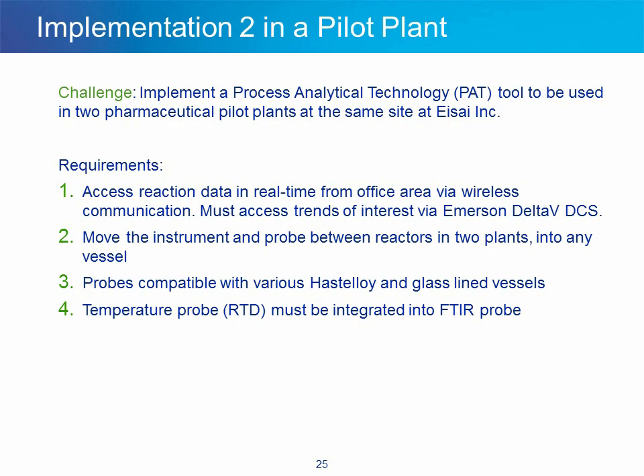Implementation number two is in a pilot plant. The challenge was to implement a process analytical technology tool to be used in two pharmaceutical pilot plants at the same site at Eisai Inc.. Requirements included: project engineers and chemists must have access to reaction data in real time from their office area with wireless communication desired; operators must have access to trends via their Emerson Delta V DCS; operators must be able to move the instrument and probe between reactors in two plants; and the temperature probe RTD must be integrated into the FTIR probe.